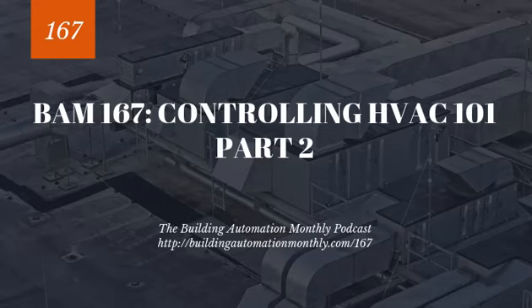They exist to pull air through the return duct into the unit in the case of a return fan, or they are designed to pull or push air down the supply duct in the case of a supply fan. So fans move air, and only when we have our safeties and our dampers under control and our fans are moving air, can we start to look at conditioning the air with our coils.